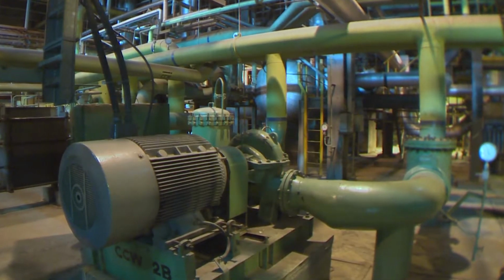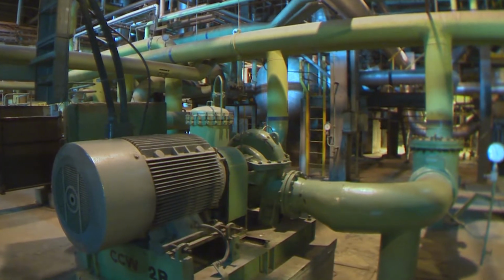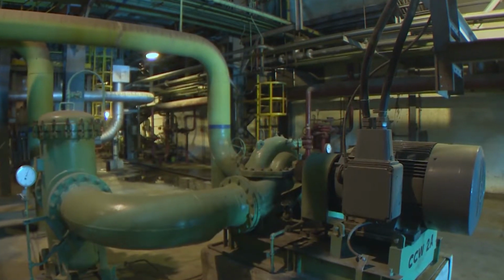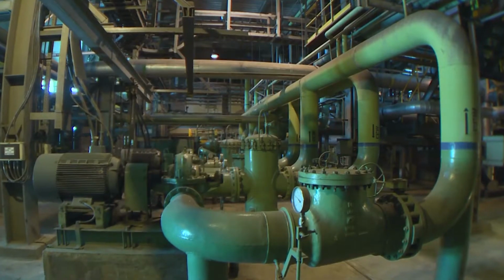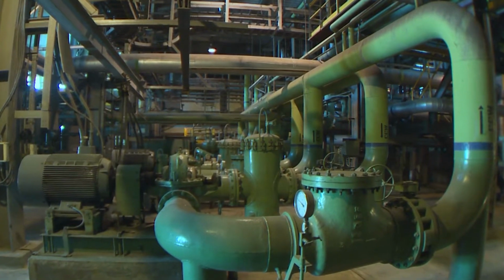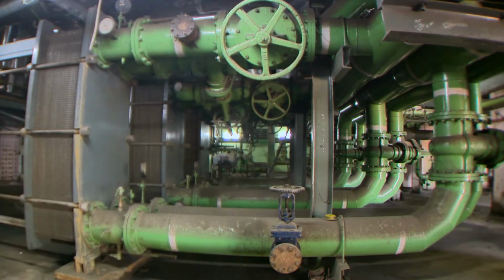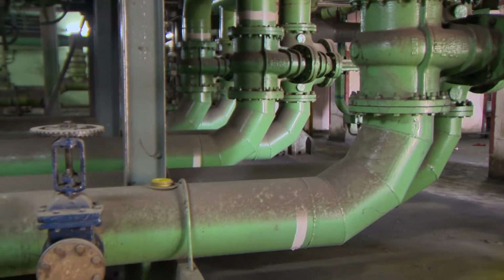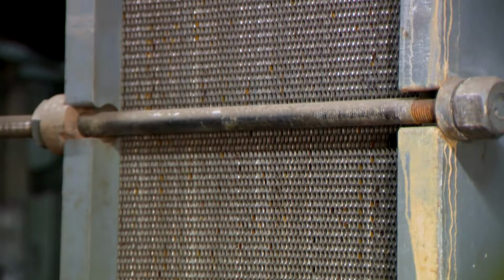Auxiliary cooling water system. The auxiliary cooling water pump supplies demineralized water to various auxiliary equipments for cooling purpose. This is a closed cycle system where the warm water is cooled by circulating water in a plate heat exchanger.